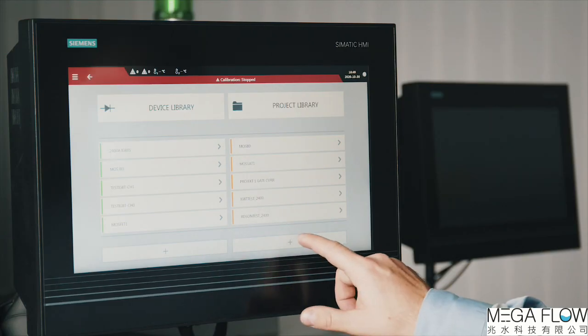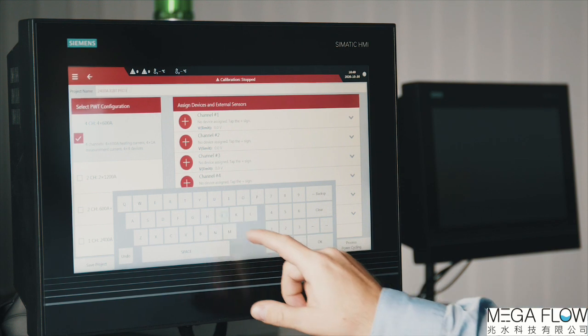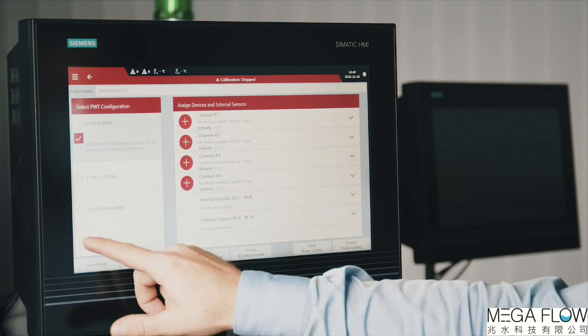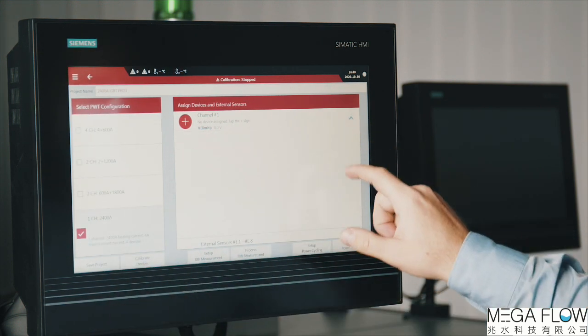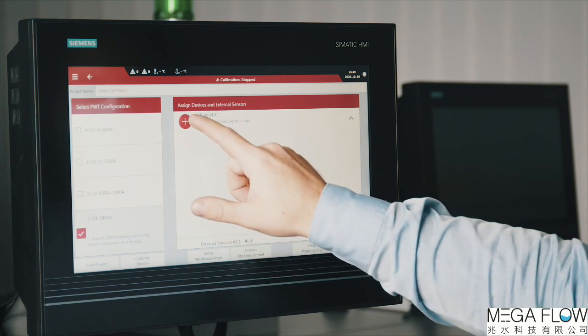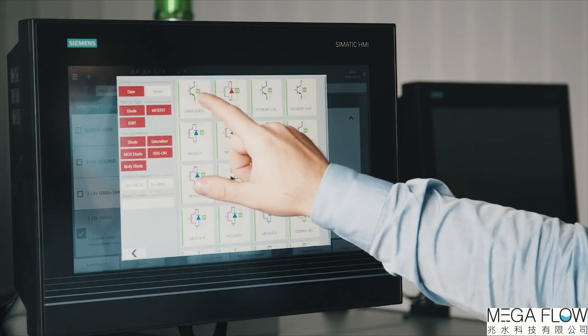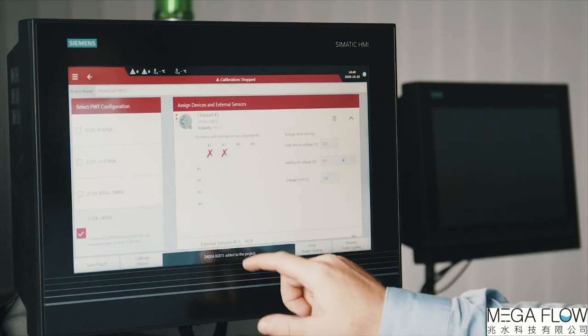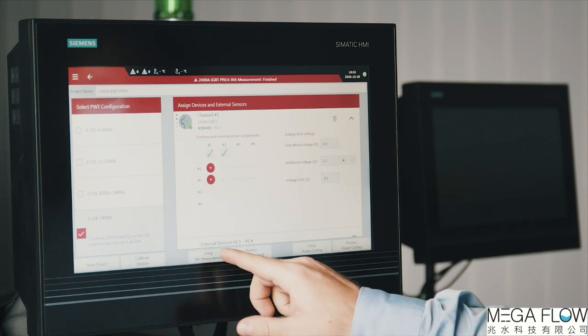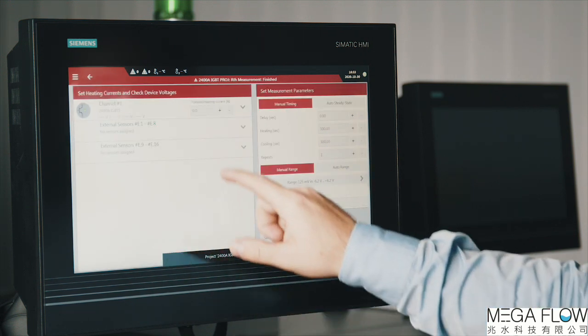For this, we need to create a new project. We need to give it a unique name, select the appropriate channel configuration to handle all 4 outputs together as one 2400 amp current source and assign the device we previously created. Thermal transient measurement can be initiated by selecting the Setup RTH measurement function.